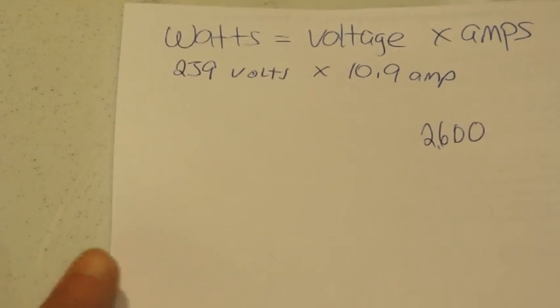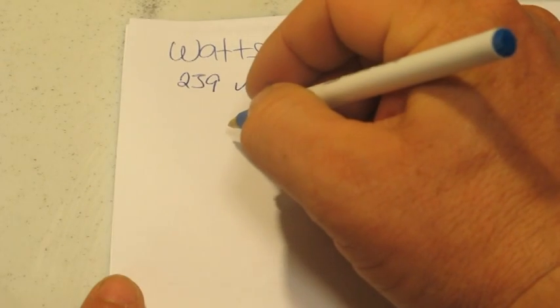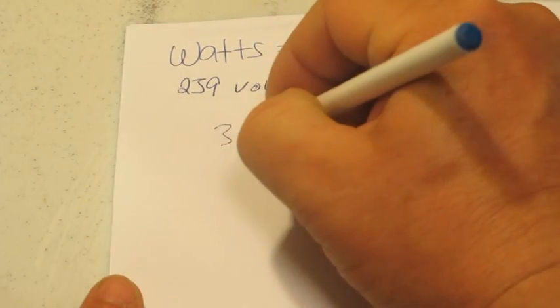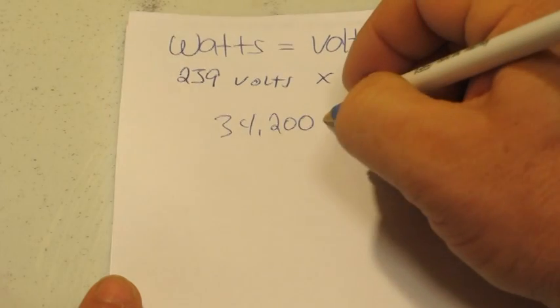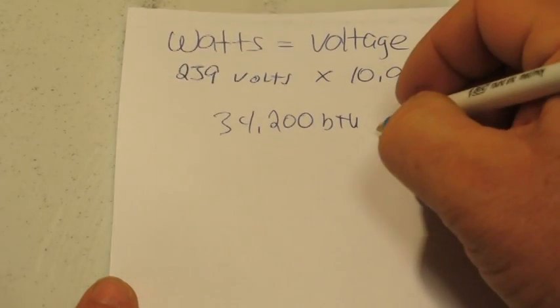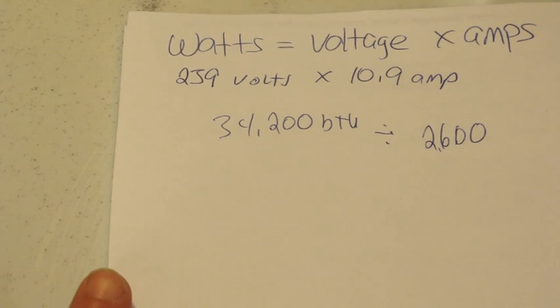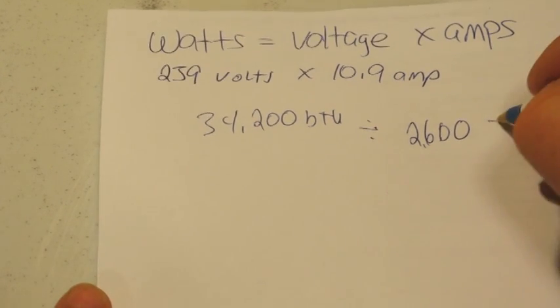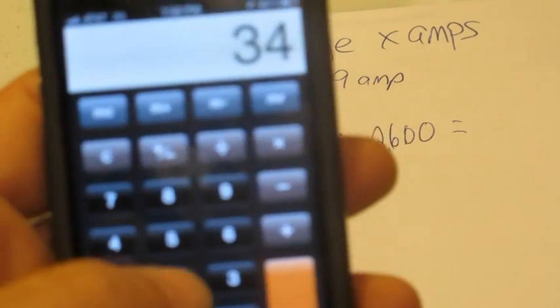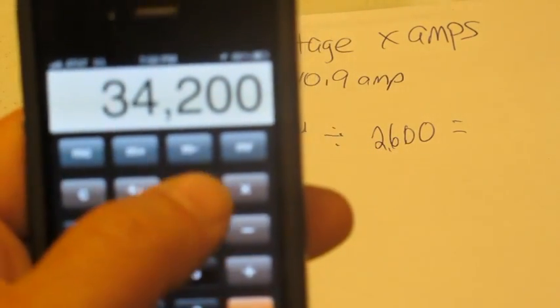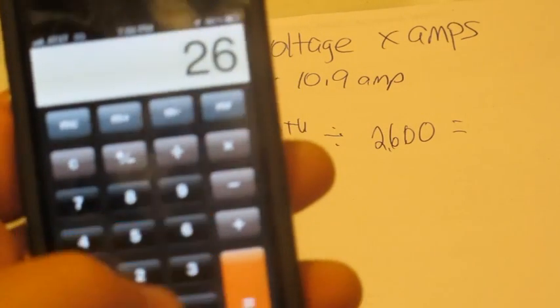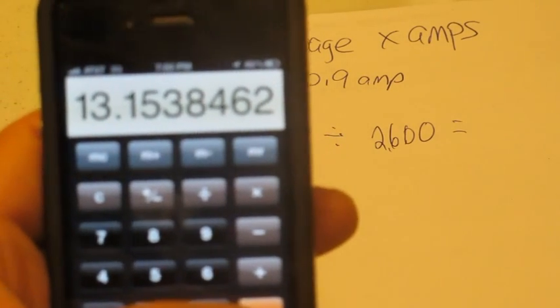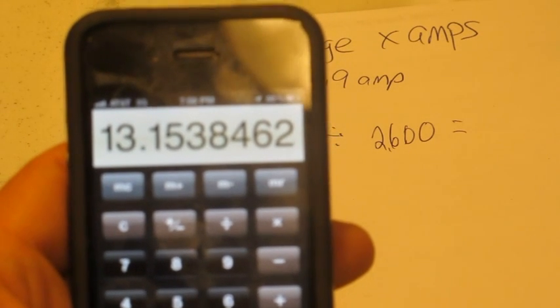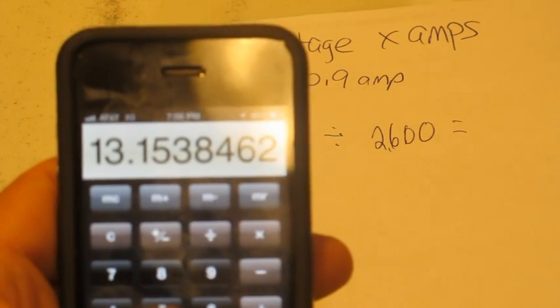Alright. Now, earlier when I measured my airflow, I was at 34,200 BTUs, and you just divide them two together, and that gives you your efficiency rating. So if I get my calculator and I put in 34,200 BTUs divided by 2600 watts, that gives me my efficiency rating of 13. So basically what that's telling me is right now I'm running at 13 SEER.